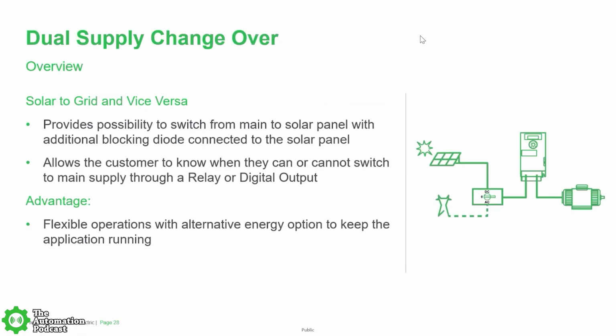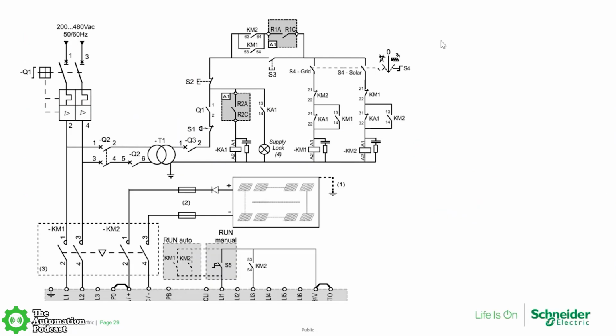One of the things that we do want to touch on is the dual supply changeover, how we can switch from the solar to the grid, and again, it could be battery power or some other source of power. It looks like quite a bit of a diagram, but it's very important that we follow the instructions in the diagram, because the VFD itself will tell you when you can switch over from solar back to main power. You have all the relay logic here, connecting onto the DC bus itself, and then the solar and main power as well through the relays connecting back to the grid.